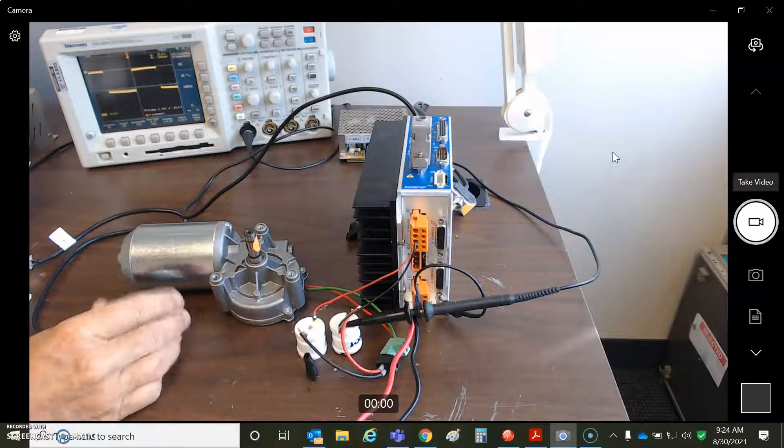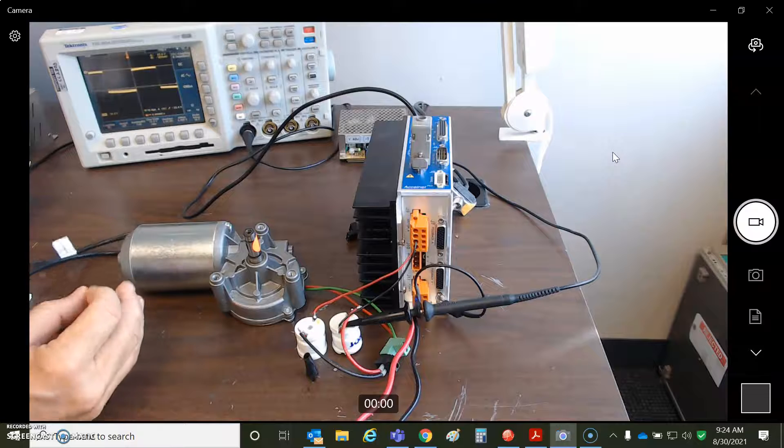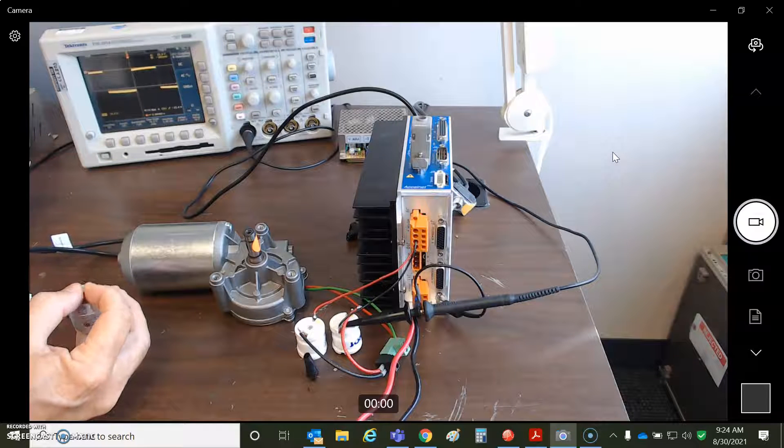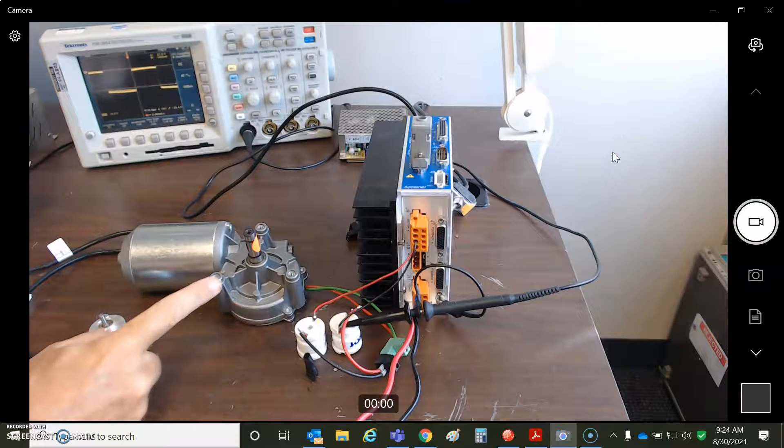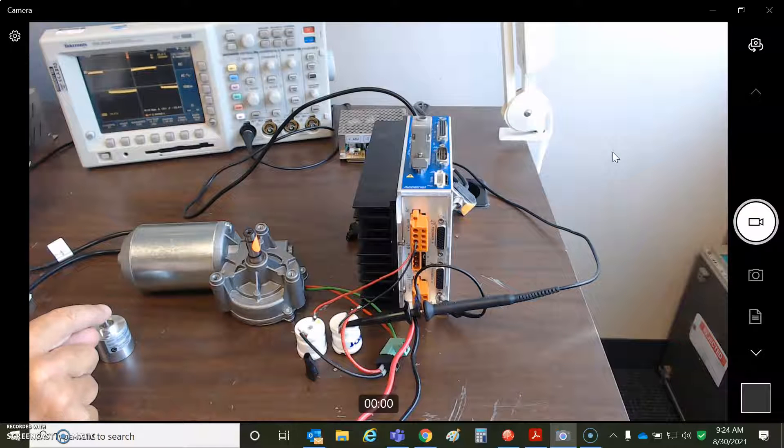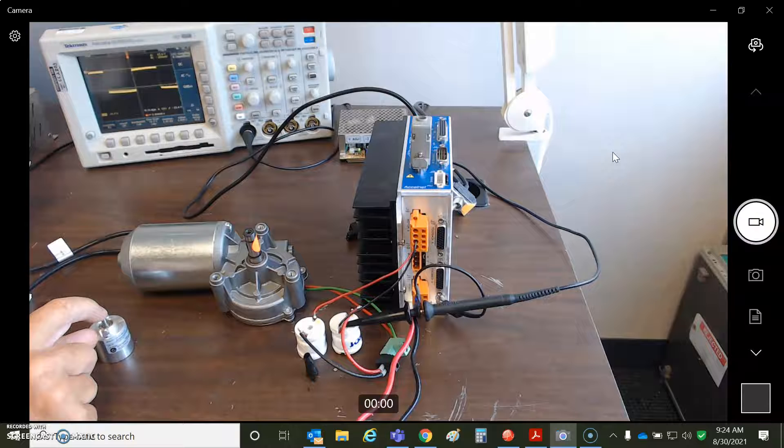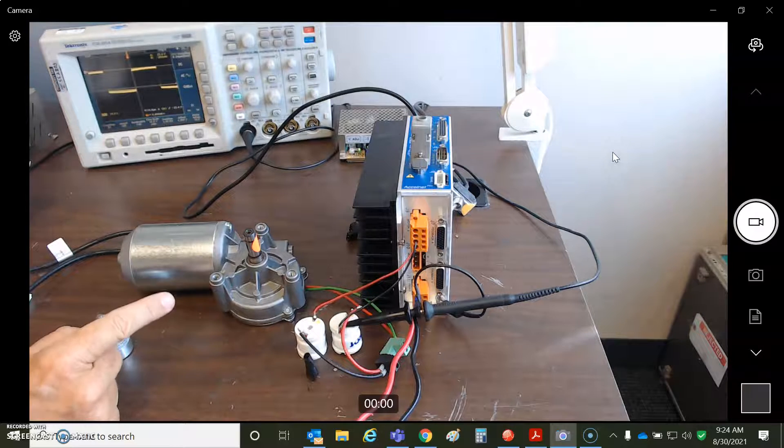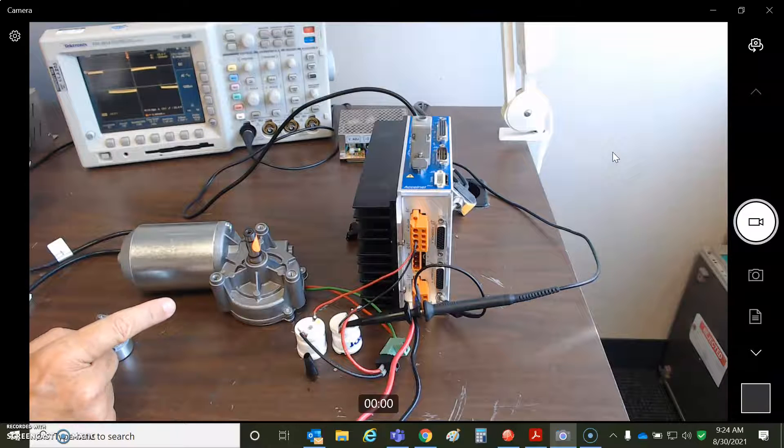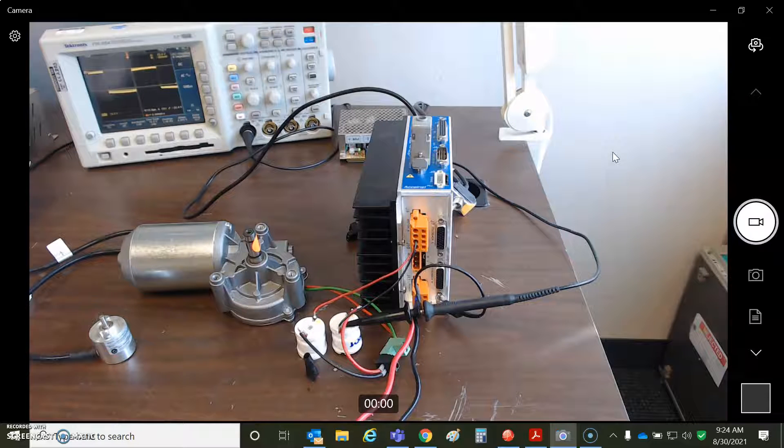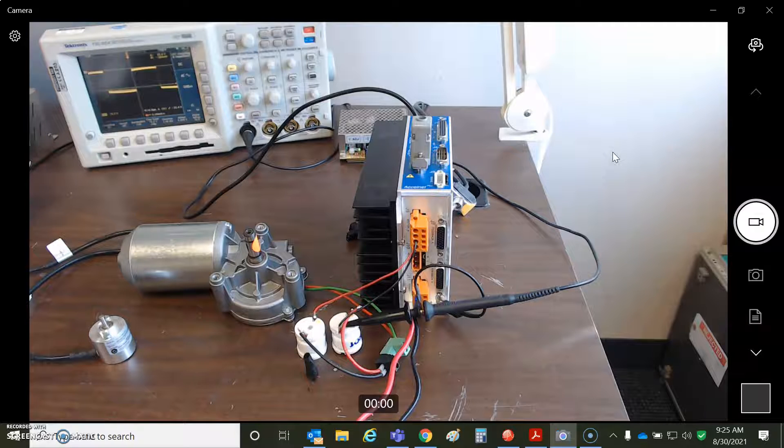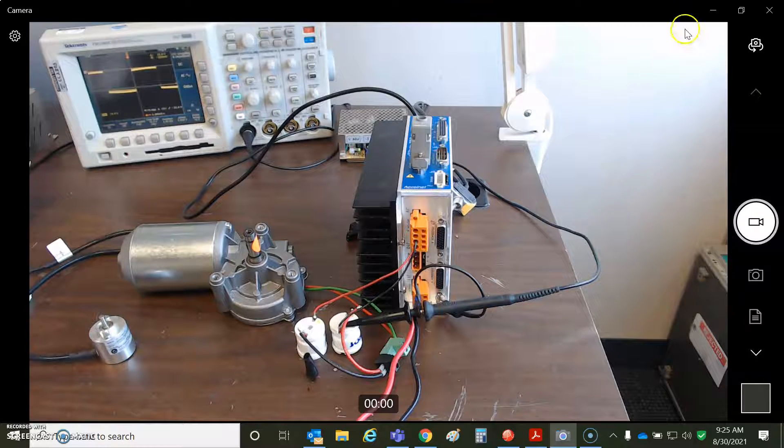But as you can see, I've also got this encoder, so what we're going to do is that attaches to the lift or the conveyor, and then on the conveyor, there'll be another rotary to measure the speed of the conveyor. As long as there's not a lot of mechanical slop between the two, we've got a nice estimated velocity in the inner loop, which will, the error between the command and an actual position, as the dual or second loop for closing the position loop, will command the voltage. It may be possible to also do this with bypassing the velocity loop and just use a PID on the position loop, but I like the stability of some inner velocity loop. But then again, it integrates, so if there's some slop in the mechanical system, put some integral in the position loop and maybe turn off the integral in the velocity loop. So, the command will always rise to make it move. Just watch out for the case of punting.